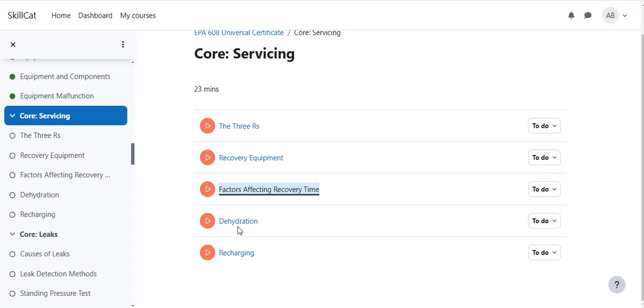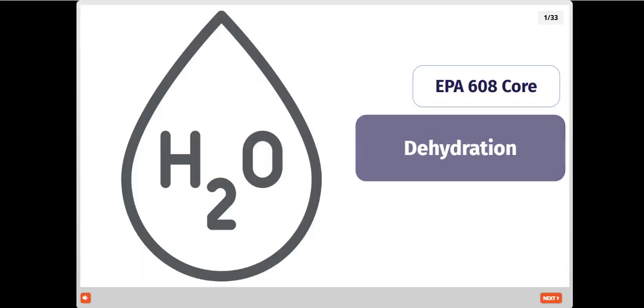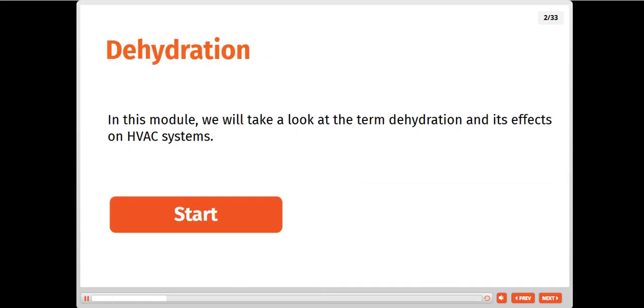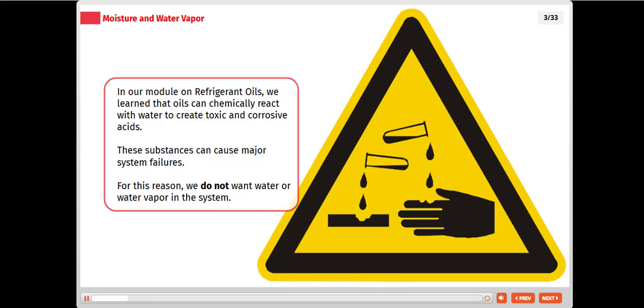Okay, the next one is dehydration. In this module, we will take a look at the term dehydration and its effects on HVAC systems. In our module on refrigerant oils, we learned that oils can chemically react with water to create toxic and corrosive acids. These substances can cause major system failures. For this reason, we do not want water or water vapor in the system.